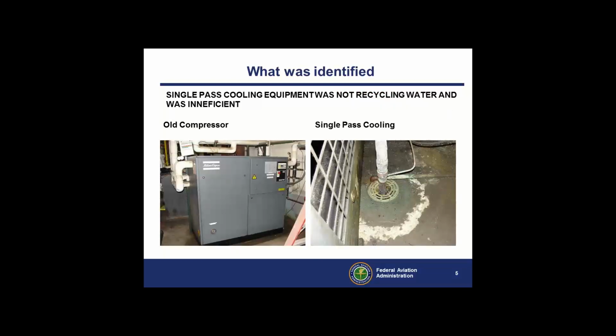Here's one thing we identified with single pass cooling systems. During an audit in one of our facilities, we found a 50 horsepower compressor doing single pass cooling, meaning it was using potable water to cool the compressor. This pipe was located on a wall by the old compressor, hidden so we couldn't see it, but we could hear it, and found this compressor was being used 24/7, using water to cool it even during evening hours when the compressor needed air, since it served the building as well as some machinery.